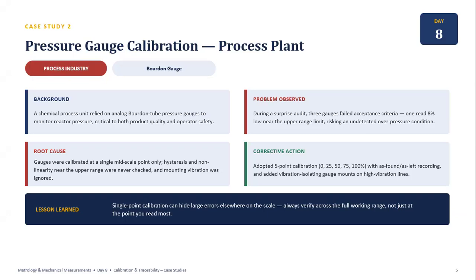The next case study is about calibration of pressure gauges. Our second case study comes from a chemical process plant where Bourdon tube pressure gauges were used to monitor the reactor pressure. During an audit, 3 gauges failed the acceptance criterion. One gauge was reading approximately 8% low near the upper range limit, creating a potential safety risk. The investigation showed that calibration had been performed at only one mid-scale point. The hysteresis and non-linearity errors at other points were not adequately evaluated, and vibration effects were also ignored.